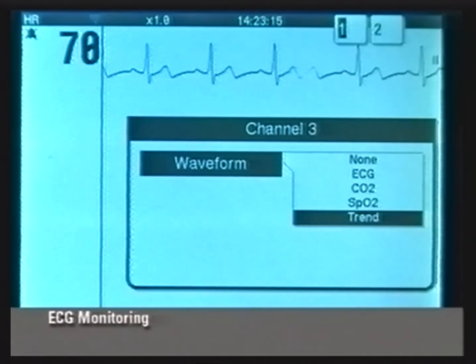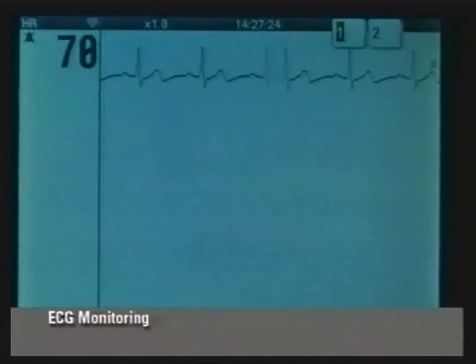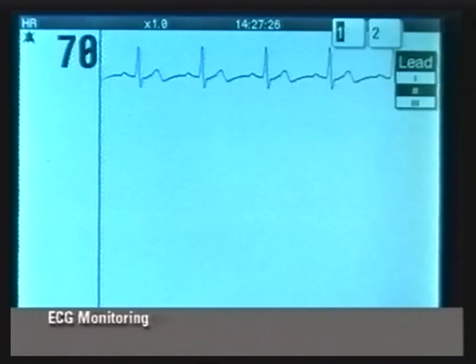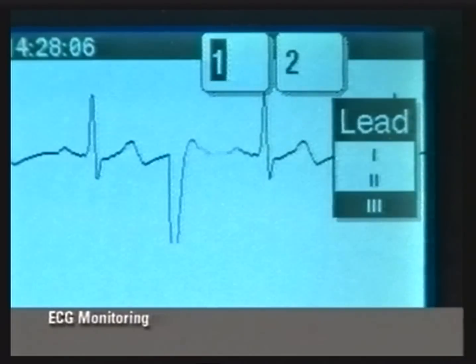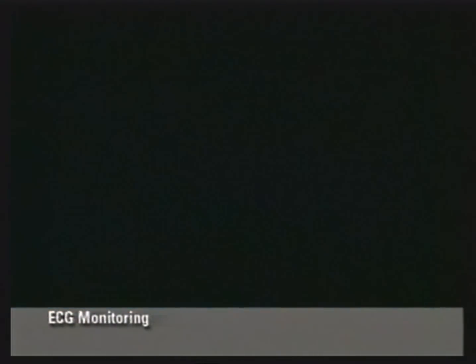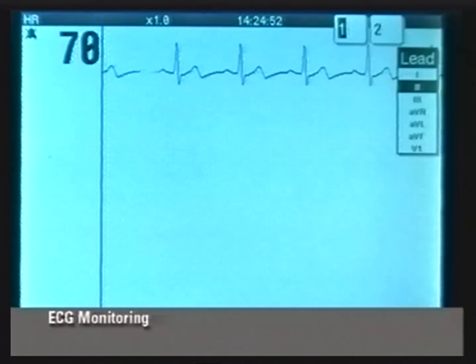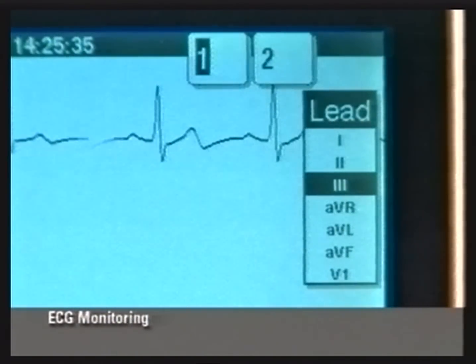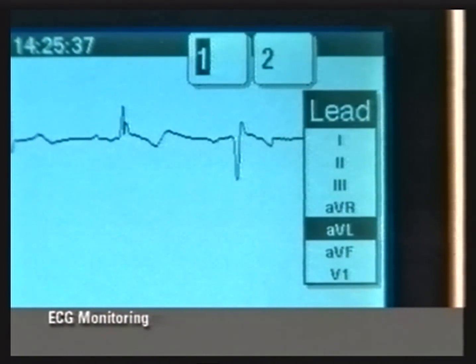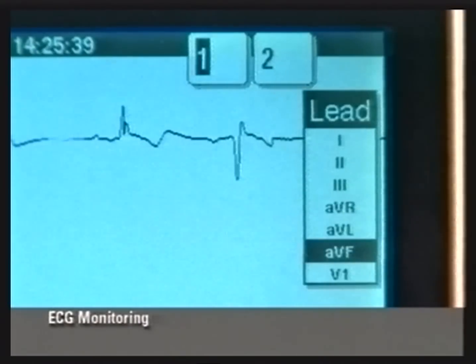Consult the operating instructions for more information about using channels 2 and 3. When the 3-lead cable is connected, only 3 limb leads, 1, 2, and 3, can be selected for ECG monitoring. When the 5-wire cable is connected, the 6 standard limb leads can be selected for ECG monitoring. In addition, the 5th wire can be placed in any of the chest lead positions.